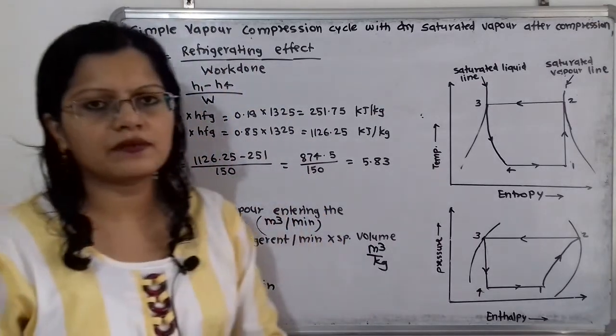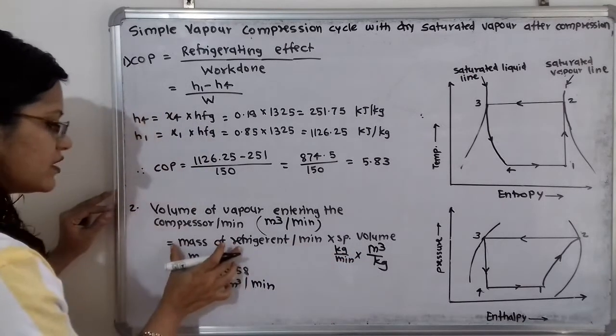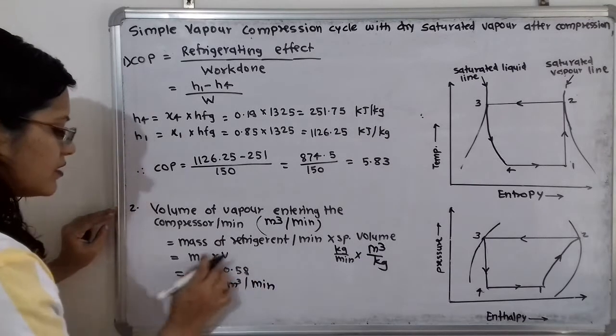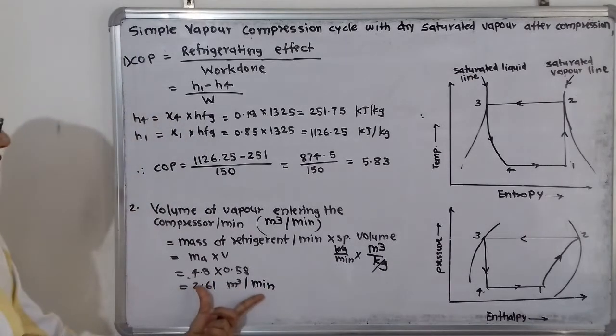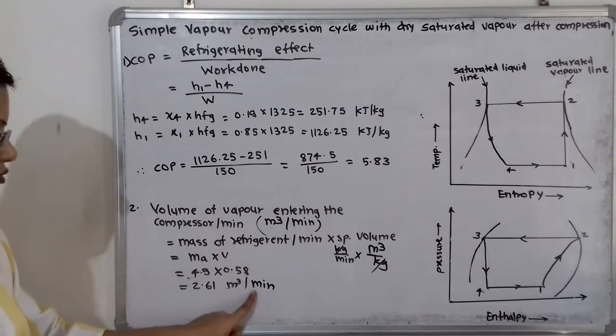To find the volume, multiply the mass circulation rate by the specific volume: V = ma × v = 4.5 kilogram per minute × 0.58 meter cube per kilogram = 2.61 meter cube per minute. The kilogram units cancel, giving the volume of vapor entering the compressor as 2.61 meter cube per minute.